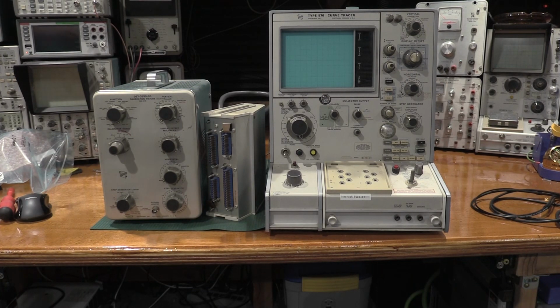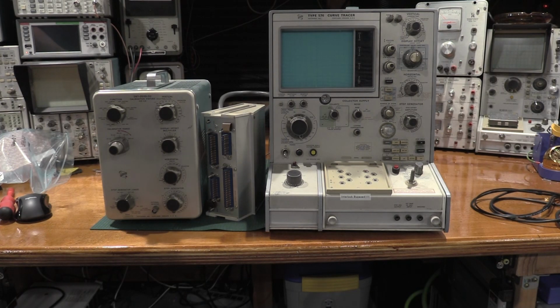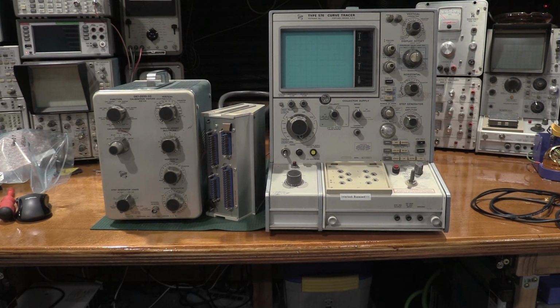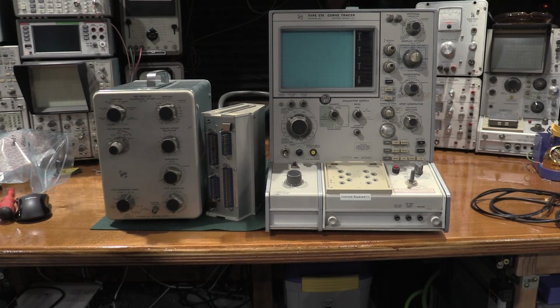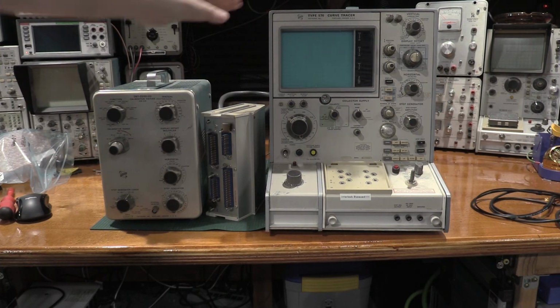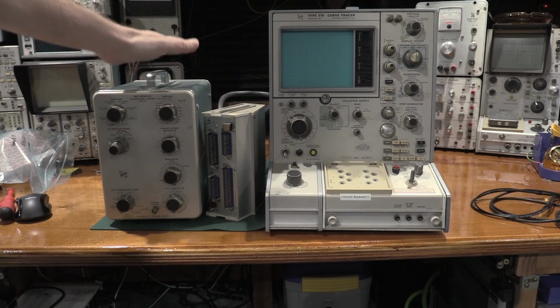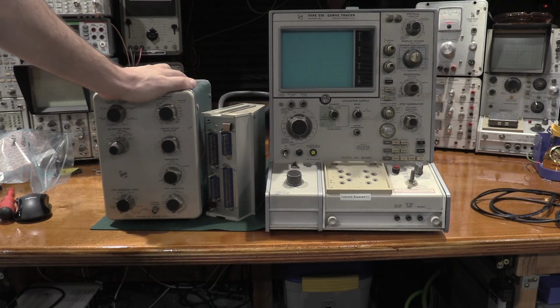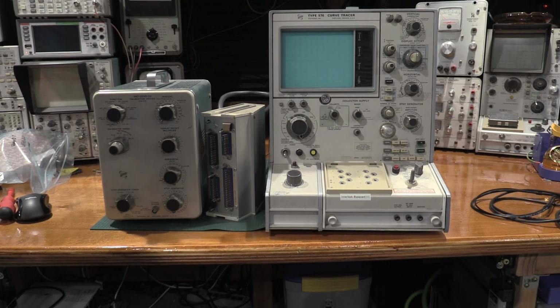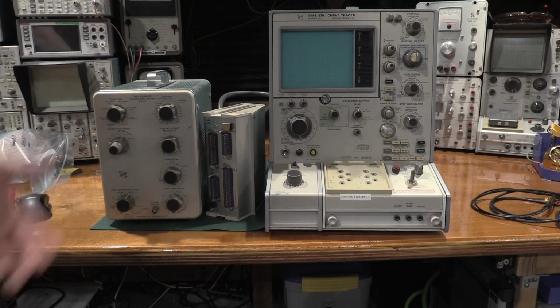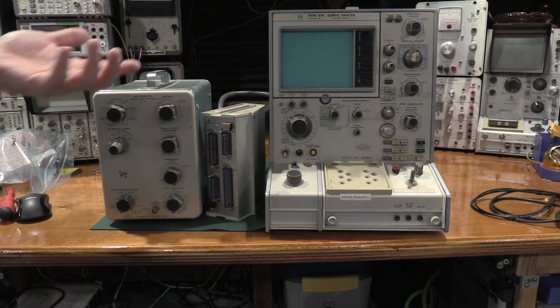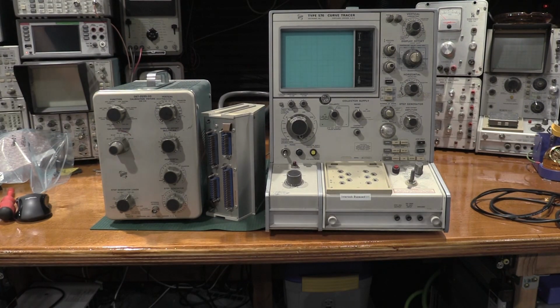Now, it's not continuous, it's pulsed, but it does do, if I remember it correctly, a 2,000 amp pulsed, or a 2,000 watt power pulse into the device under test. It is possible to do one of these without the calibration fixture. There is no calibration fixture for a 577. So Tek decided to get away from that, and they sold a calibration kit, which was essentially a couple capacitors and resistors that you bought that they tested and were certified good enough to do an alignment.